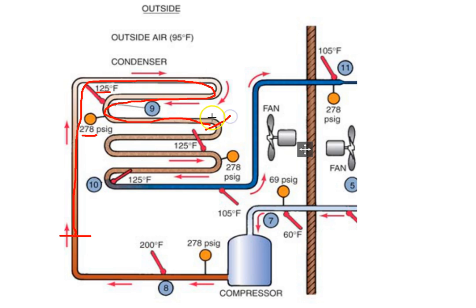Theoretically, halfway through the condenser, we are 50% liquid, 50% vapor. As we move down through the condenser, we get to the point where we have removed all of the latent heat and we are 100% liquid. And then the PT chart stops right here because now we're 100% liquid. And remember, the PT chart talks about saturation, and that is when we're at both vapor and liquid at the same time. So we've removed the latent heat from this point to this point in the condenser, and this is what the PT chart refers to. Throughout this condenser, the temperature remains 125 degrees Fahrenheit as long as we are changing state from vapor to liquid. Then when we hit this point, we begin to subcool.